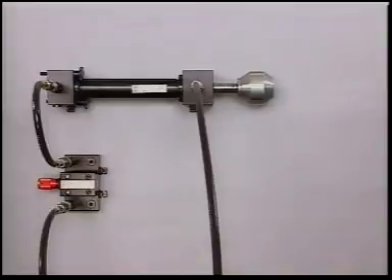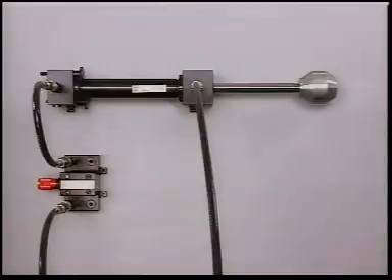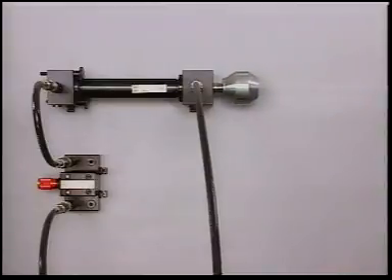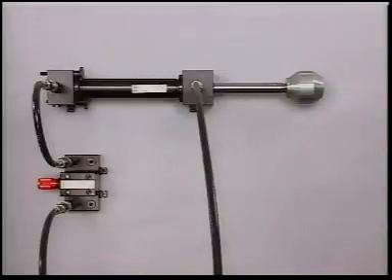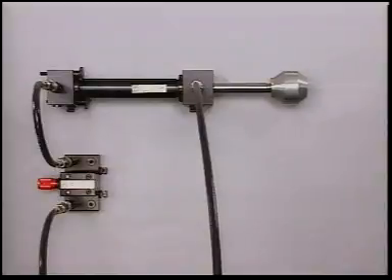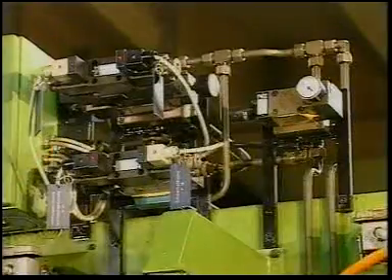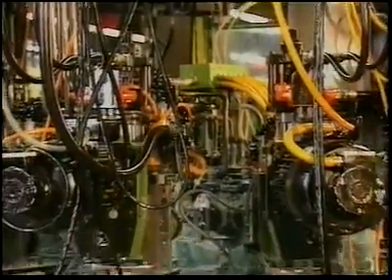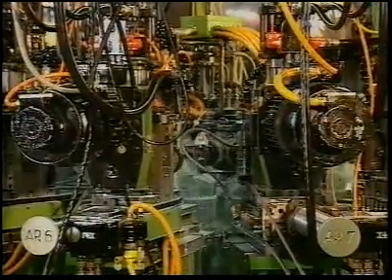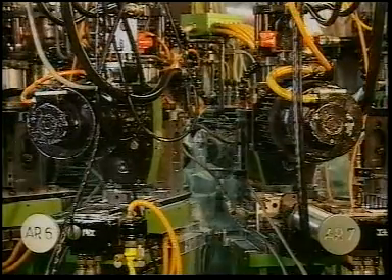There are two ways to control the flow rate. Here we see control of oil supply. Restricting the flow in the supply line for advancing the piston causes the oil to heat up, but warm oil reduces the precision of piston motion in the cylinder. In some machines, this is not important, but this machining complex requires greatest precision, so that any rise in oil temperature is undesirable.